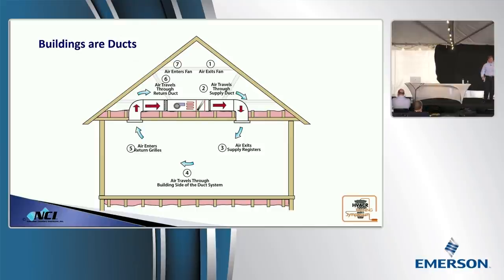Now, the building side of the duct system is what makes the connection from the supply air coming out of the supply registers in that illustration back to the return grill. Now, for a duct system to work right, what are some of the aspects that it has to have? Ducts need to be leaky or tight? Got to be tight, right? You can't control air unless you can contain it. Well, what about balancing dampers? Is it a good idea to have dampers to control airflow? Yeah. What about insulation? Got to have insulation. Yes, please. Got to have insulation because we're trying to reduce what? Heat loss or gain, heat flow.